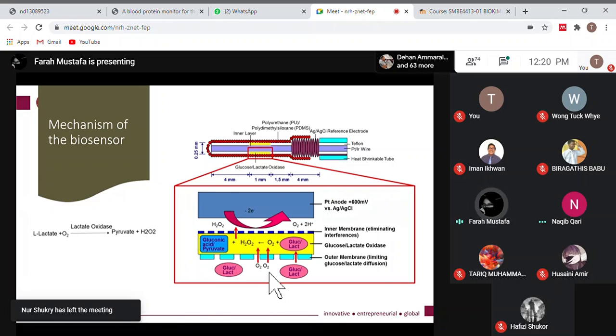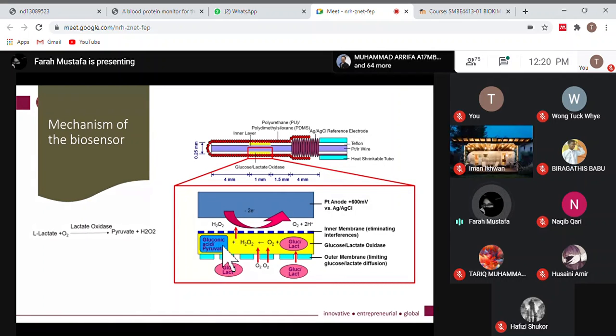So it implements the immobilization technique of the enzyme, which is the oxidase, and uses the amperometric biosensor technique. So by referring to the image, the outer membrane here acts as a filter by only allowing lactate to enter to the region with the enzyme, and also to prevent the high influx of lactate. So once inside, the lactate molecule will react with oxygen and be oxidized by the lock and key principle. It will convert lactate into pyruvate and produce hydrogen peroxide as the byproduct. So the hydrogen peroxide will then be reduced into oxygen and also hydrogen. And the current produced from the reaction is used as the quantitative measurement of the lactate concentration.